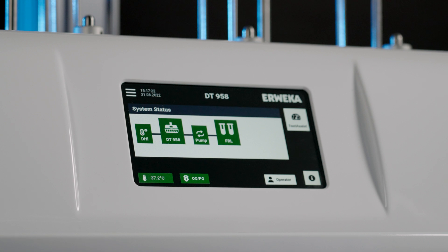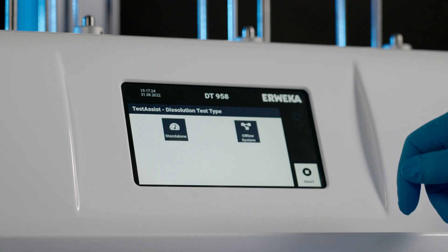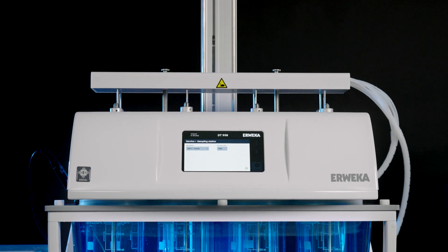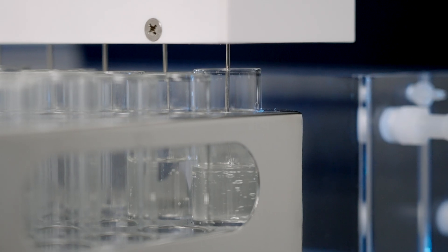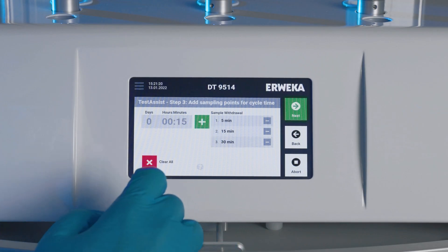TestAssist now offers two testing modes: the stand-alone testing mode and the new offline testing mode, which enables TestAssist to control the connected automatic sampling station, pump and sample collector for fully automated, highly precise sample taking and sample storing at user-defined time points.